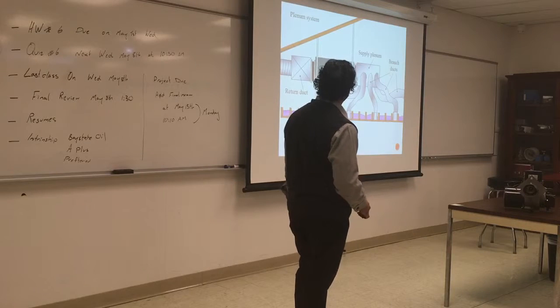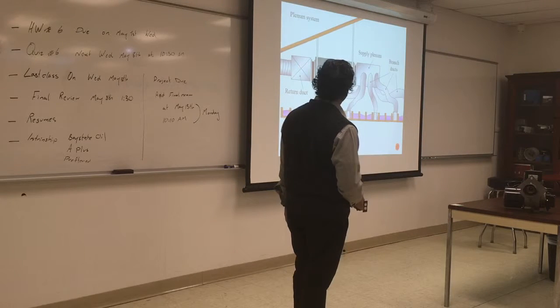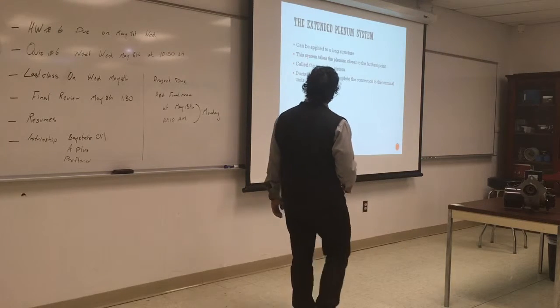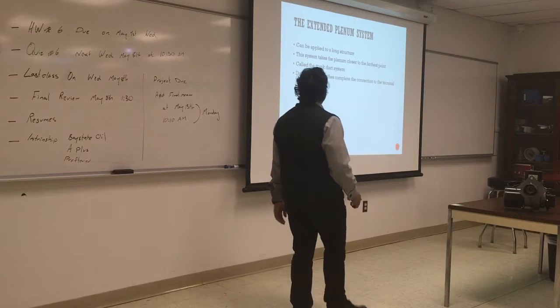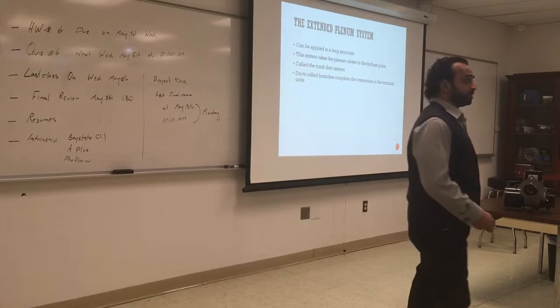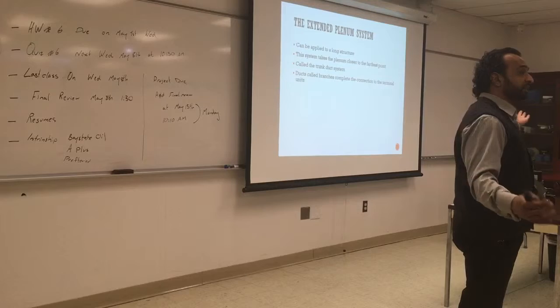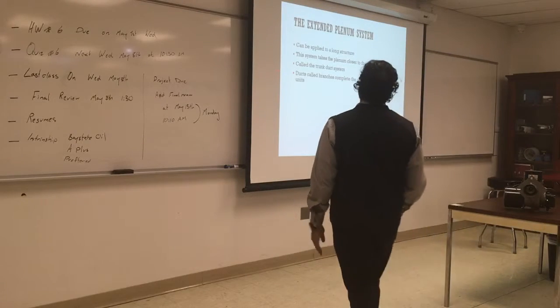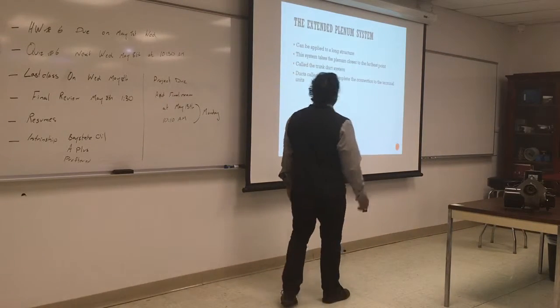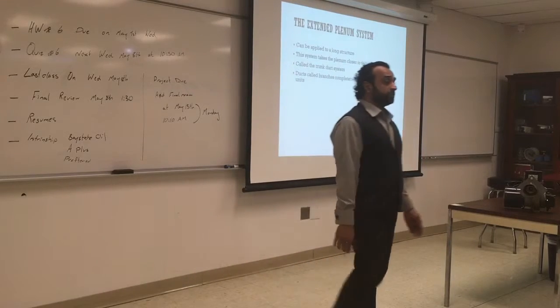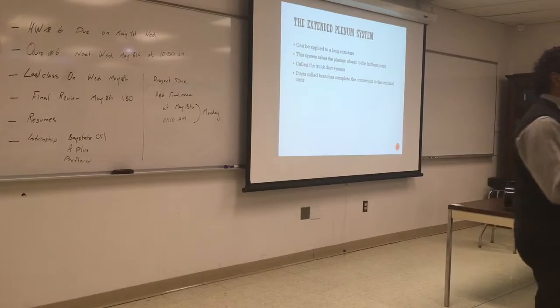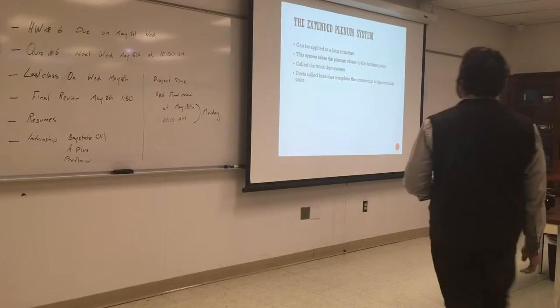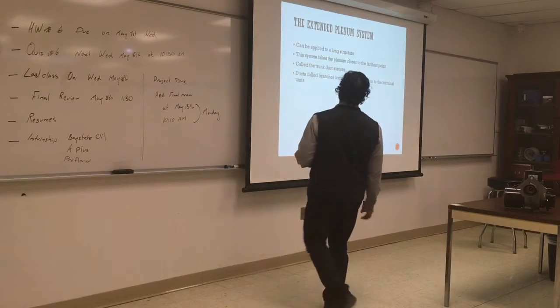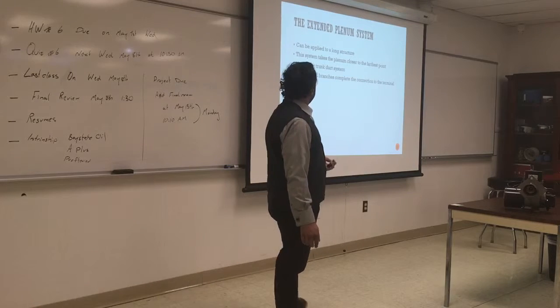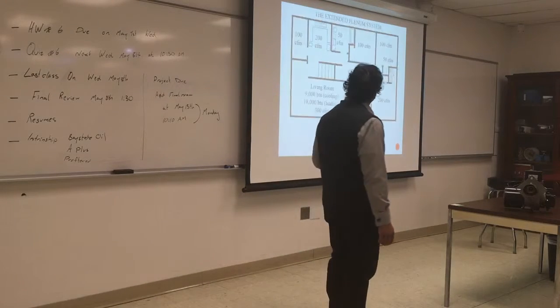So that's the plenum. And this is going to be our return coming from the major return. So, the extended plenum can be applied to a long structure. If you have a very long structure, where you have the boiler on one side and at least a 100-yard long house, you take the plenum all the way to the furthest point, which maintains the pressure and the temperature in the entire trunk. They also call it a trunk duct system. Ducts called branches complete the connection to the terminal units. And this is what it looks like.